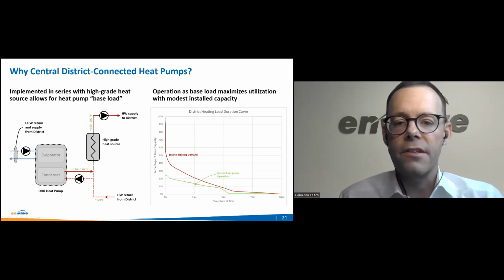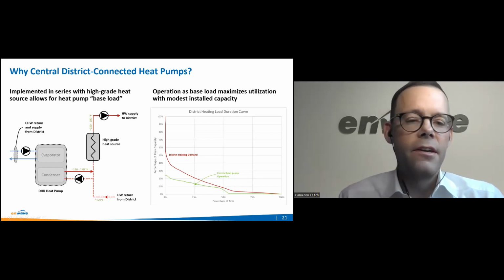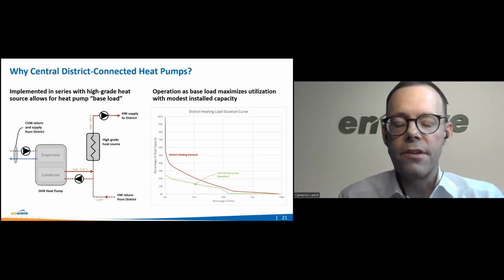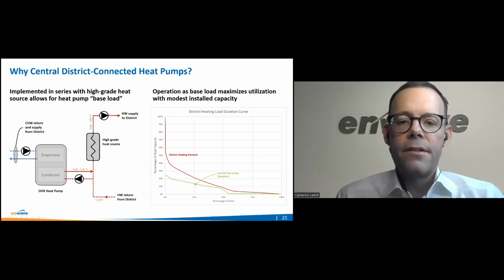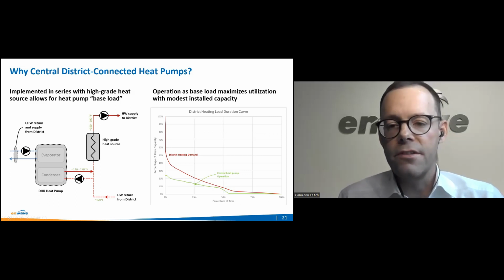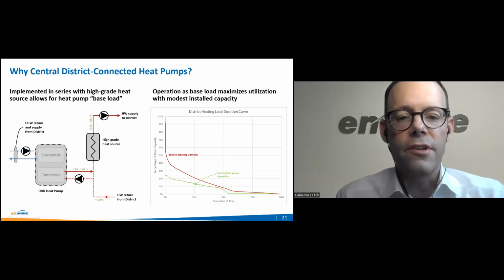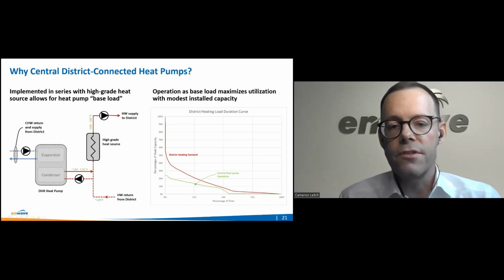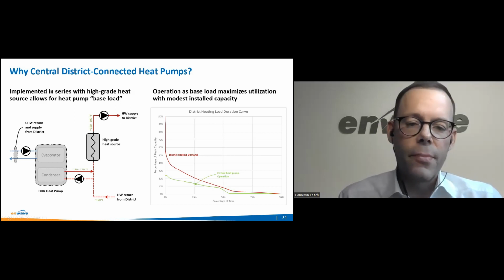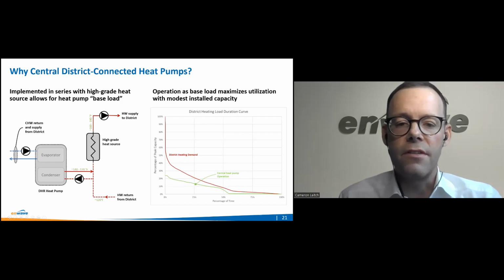Heating water returned from our customers at around 120 F is routed first through the heat recovery chillers before being topped up by downstream high-grade heat sources. This configuration has several merits, but the 2 primary benefits are simplified operation, in that the heat recovery plant only has to maintain leaving chilled water temperatures, and high utilization. This high utilization results in significant impact with relatively modest installed capacity.